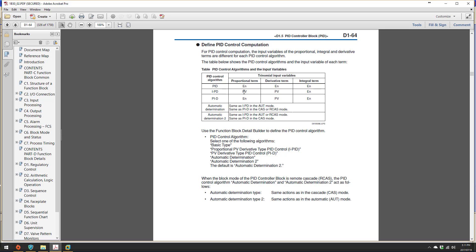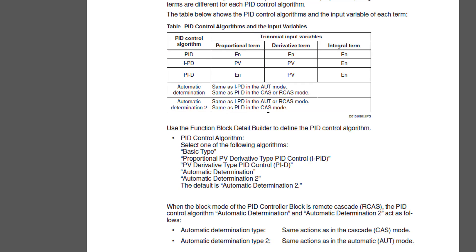The default is automatic determination type 2. Read this very carefully: it says that when in cascade mode the block will behave as a PI-D, otherwise it will behave as an I-PD. So if you have a flow loop which is a slave and you take it into auto, it's going to behave in an I-PD fashion, and the minute you place it into cascade it's going to behave in a PI-D fashion. This is the default setting.